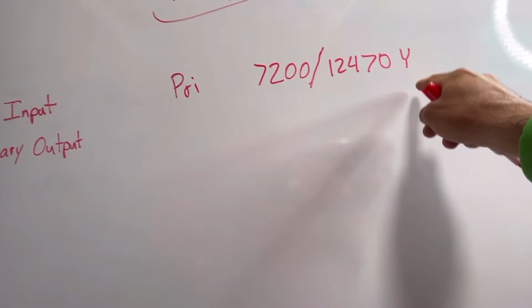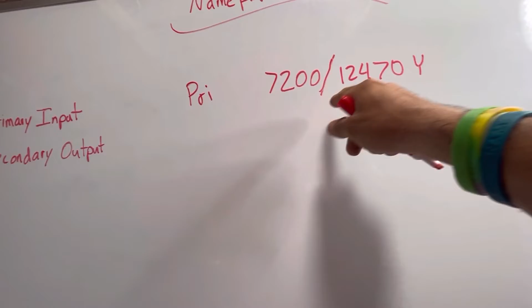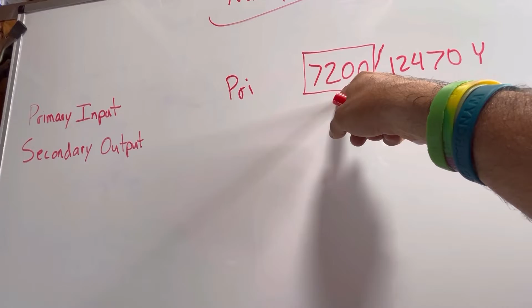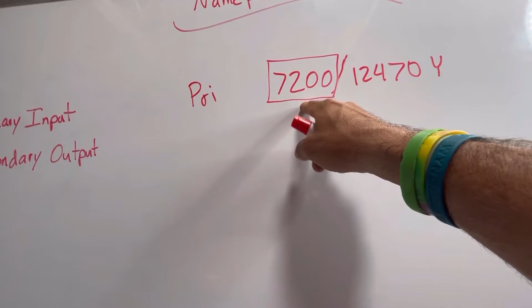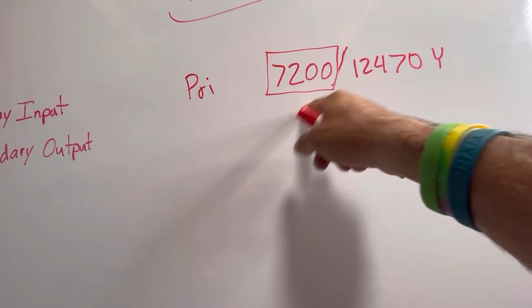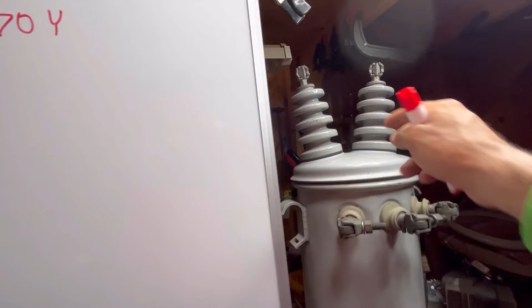There are some specifics on one of the types of nameplates that it is specific to the type of circuit it has to go on and how it has to be hooked up. But in this specific transformer right here, all this is telling you is that I need 7,200 volts. So when a transformer nameplate gives you two voltages like this, it's always going to be the smaller number. That's the one that you're going to want to put into that transformer. Another piece of information that this transformer is giving us, when it gives us the information like this, phase-to-neutral / phase-to-phase voltage, Y, what it's actually telling you is that this transformer has two insulated primary bushings, just like this one right here. So H1, H2, they're both insulated and on top of the transformer.